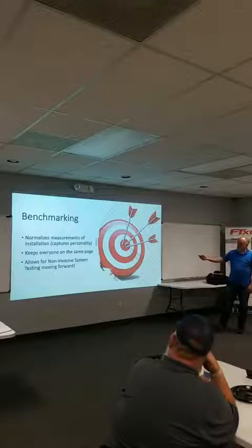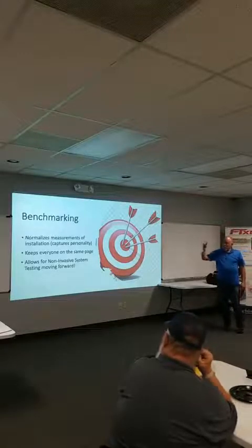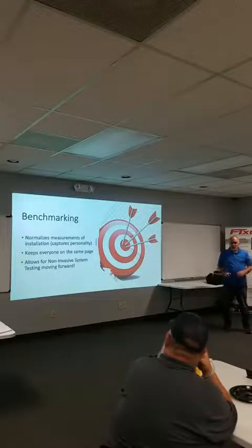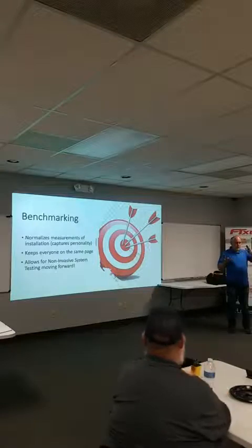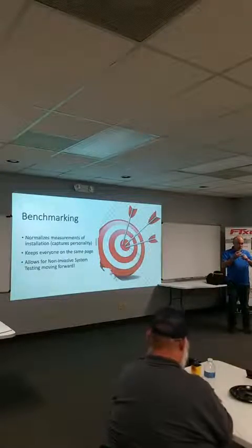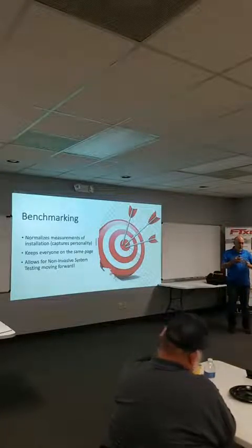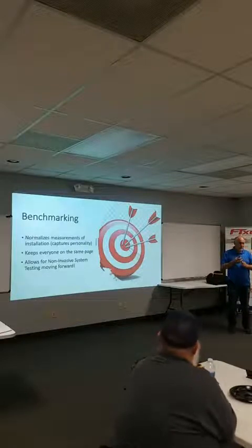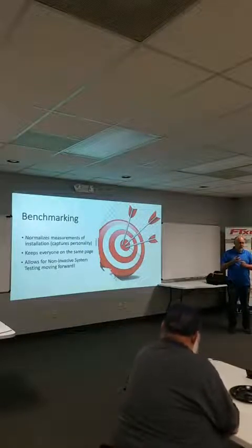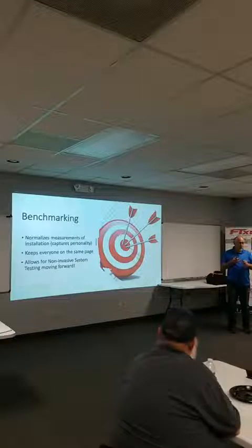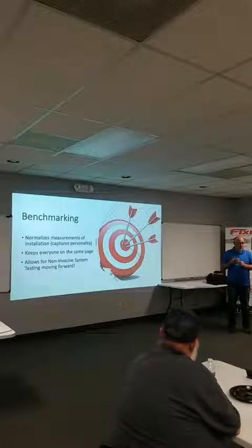fine. All right, so we're gonna benchmark that system. What this is gonna do is, when you benchmark it in Measurequick, it locks in your design temperature difference for your evaporator, your condensing temp over ambient, CTOA, how much hotter the condenser is than the outdoor air, and how much colder the evaporator is than the return air. Those things do not change. Your superheat, if it's a TXV, will remain the same at the evaporator outlet. That's the TXV's job, to maintain constant superheat.